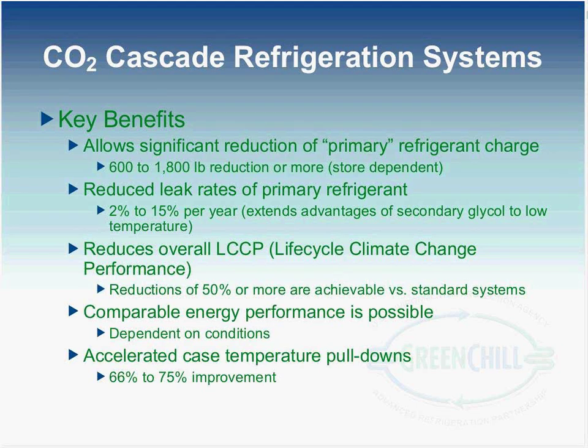And then we also see a significant reduction in leaks for a variety of reasons, which is that the HFC refrigerant is typically going to be restrained to a small area. And as a result, it's going to have a lot less piping. So not only is there a lot less refrigerant to leak, but with fewer joints, you're going to have significantly reduced potential there as well. Because of those two items and a variety of others, it does allow you to reduce the LCCP, or life cycle climate performance, pretty substantially.